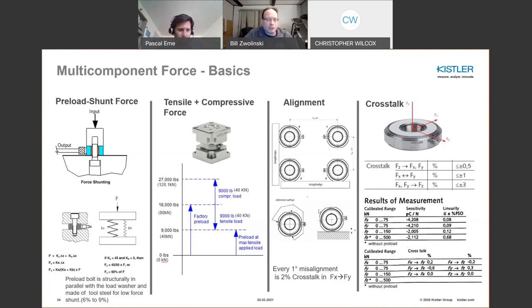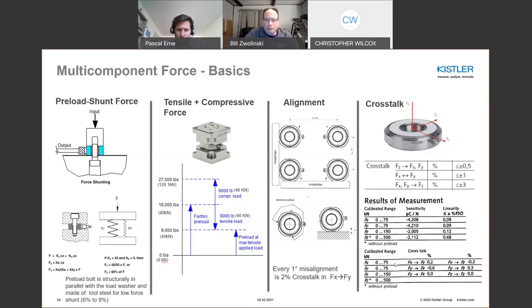In terms of dynamometry, alignment is always critical. These sensors look round but have flats on them that you can use to align the X and Y axes properly when building the fixture. For every one degree of misalignment, you incur a two percent crosstalk in X and Y — a sizable amount. Crosstalk is specified on any multi-component force sensor data sheet, but the actual calibration certificate from the manufacturer will show the measured crosstalk, which is often considerably less than the data sheet specification.